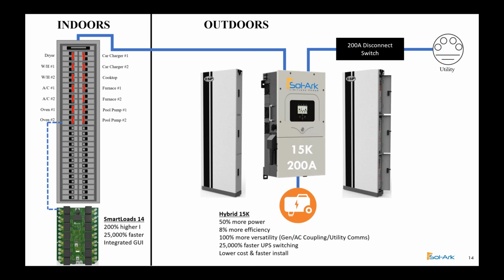But it does two things for you. Number one, if you go off grid, it lets power from the Sol-Ark come over to these top 14 circuits and run everything, and it can load shed and turn stuff on and off so breakers aren't tripping. That's what it does. It also allows you access to the whole panel.